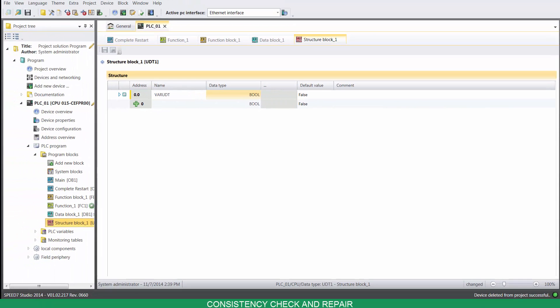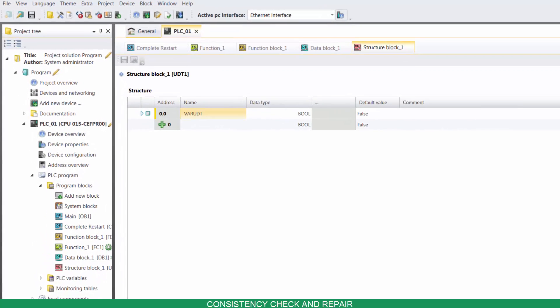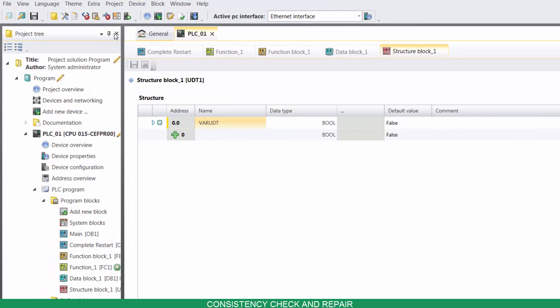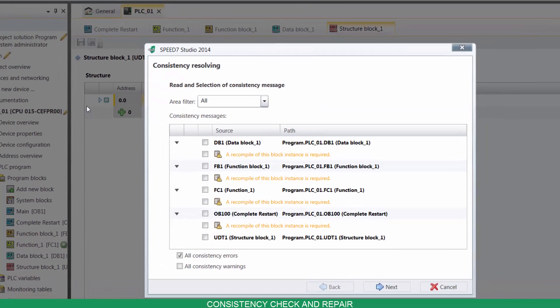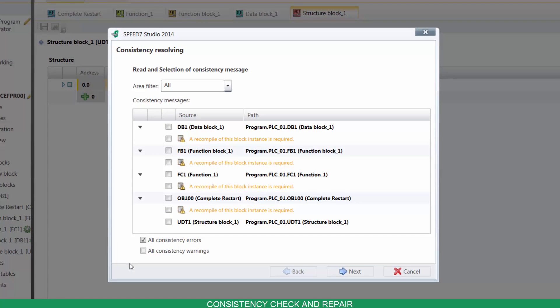If you edit blocks, inconsistencies can arise, such as interface conflicts between two blocks. Transferring inconsistent blocks to the control can lead to processing errors in the user program. To check and repair inconsistencies, go to Project, then click on Consistency Check and Repair. Now you have a list with all the inconsistencies. Click on Next to repair them.